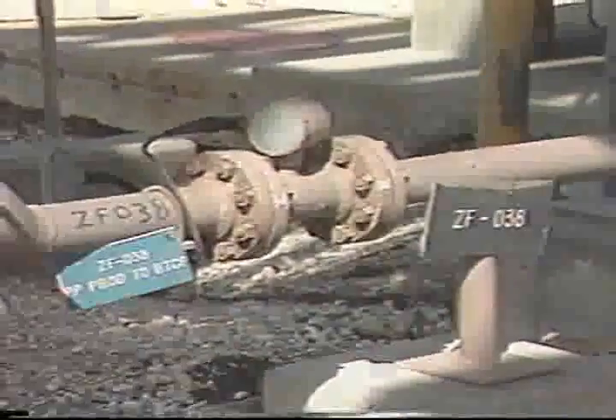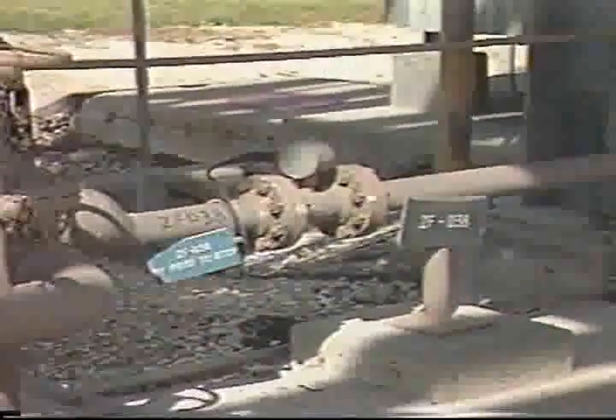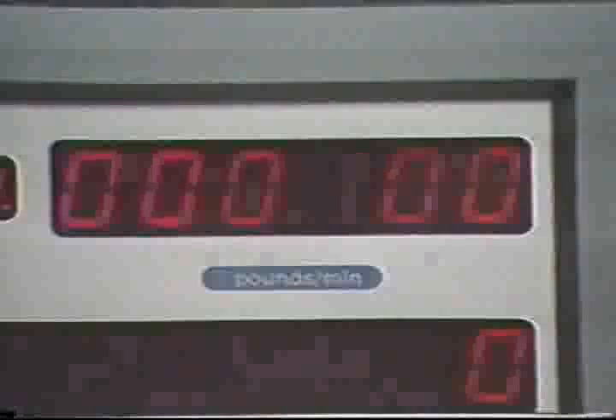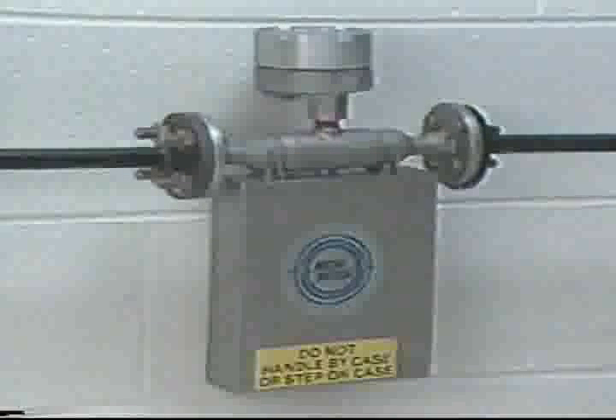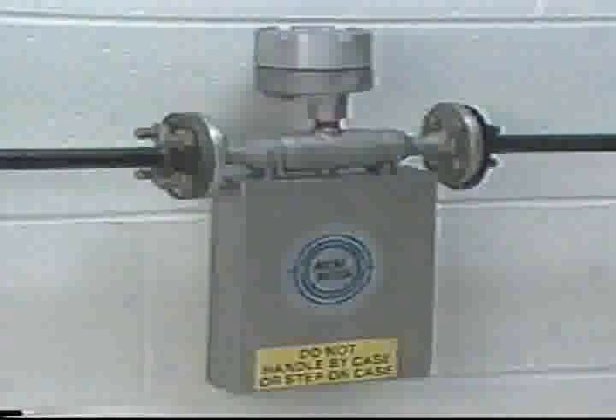It's sometimes necessary to measure mass flow for precise measurement requirements. A mass flow meter measures flow rate in weight per unit time rather than volume. This measurement is independent of temperature and pressure. Other flow meters which use volumetric measurements can be affected by changes in pressure or temperature. When the flow through a mass flow meter is increased, the output also increases, and when flow is decreased, the output decreases. In this program, we've chosen to calibrate a smart mass flow meter.